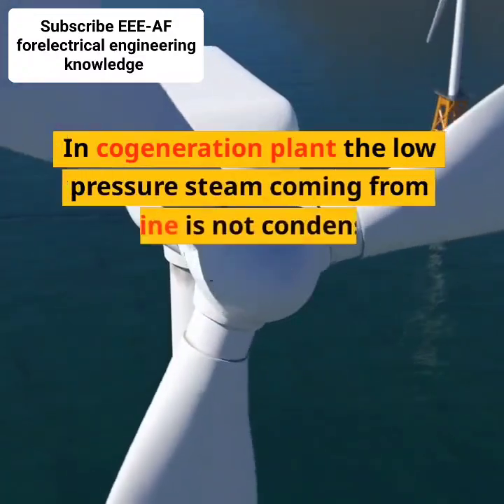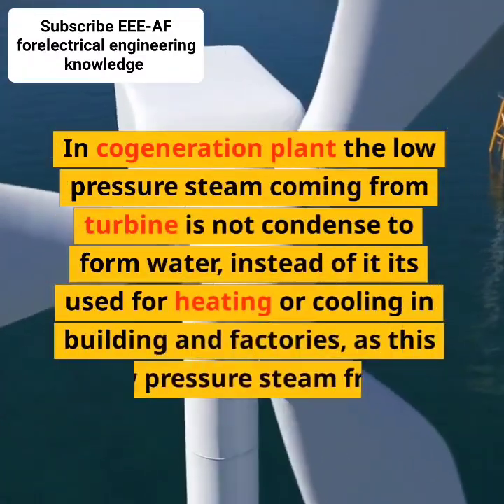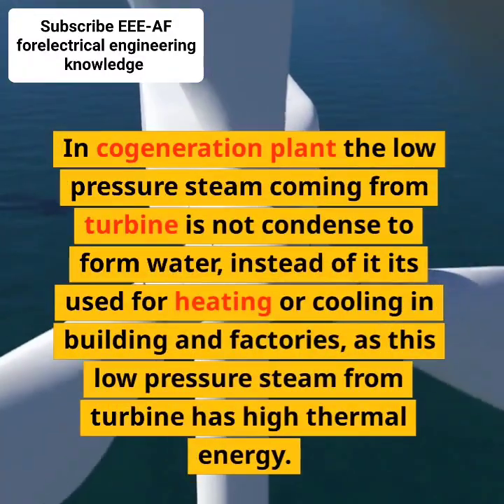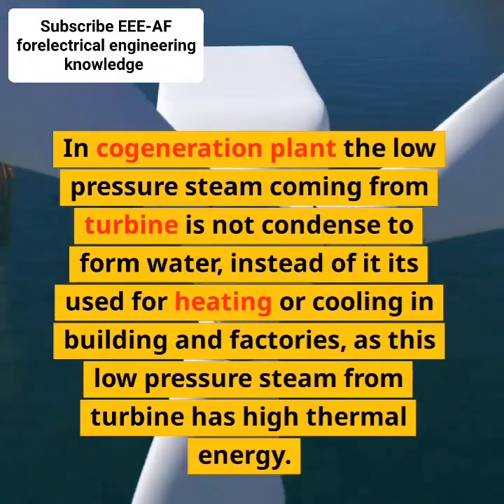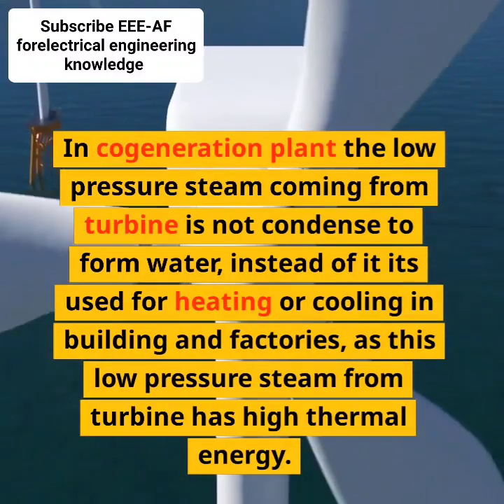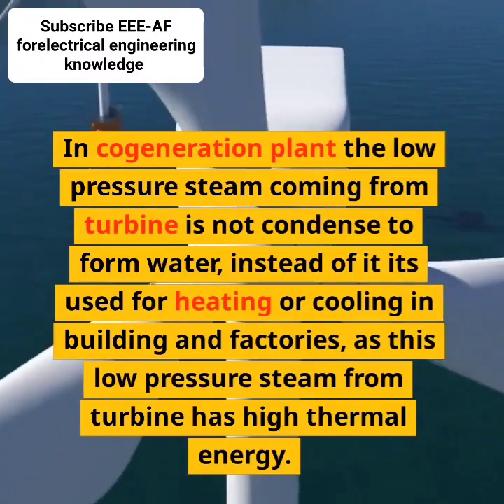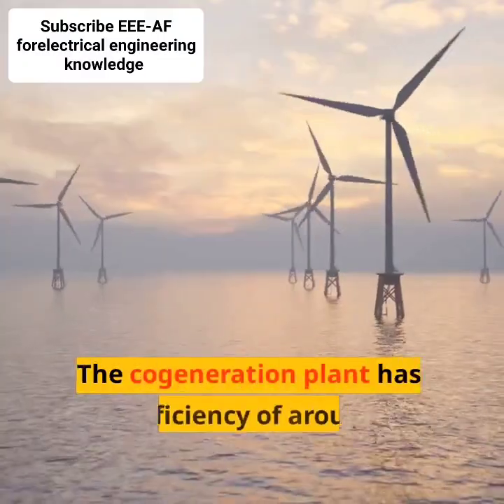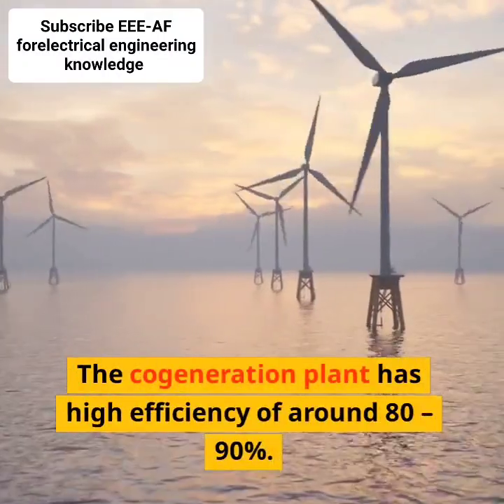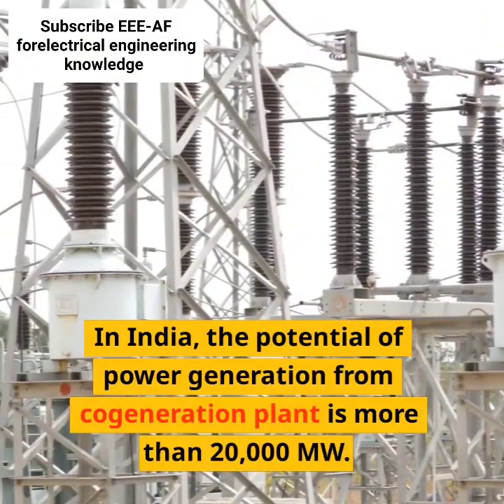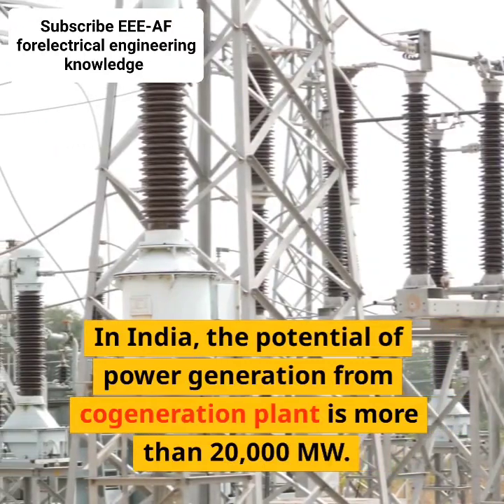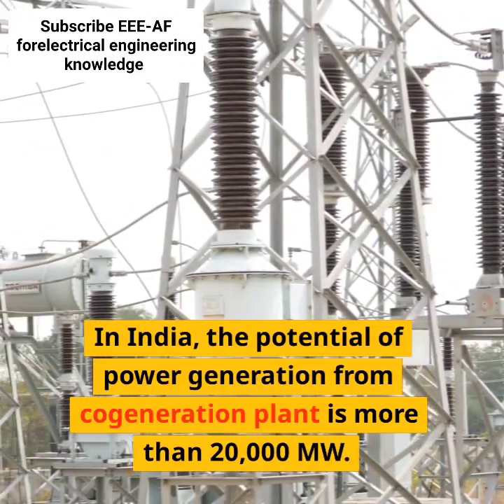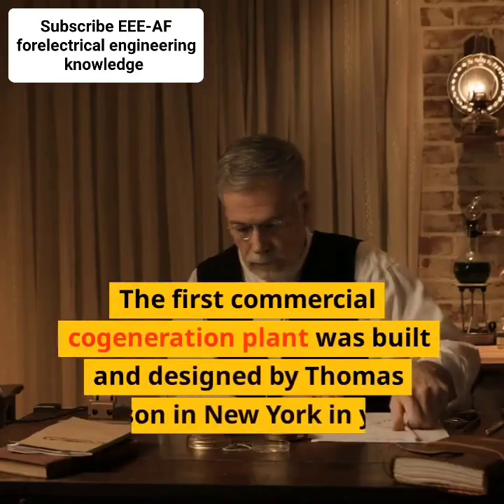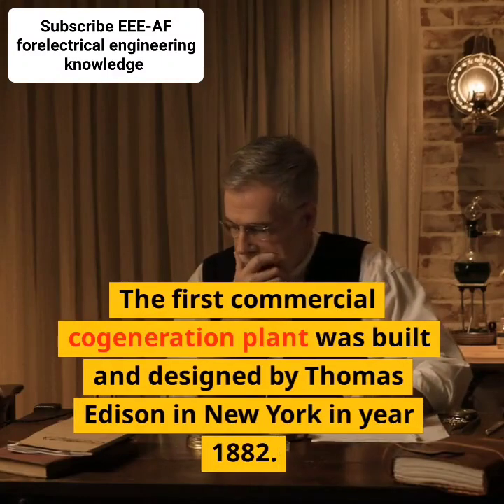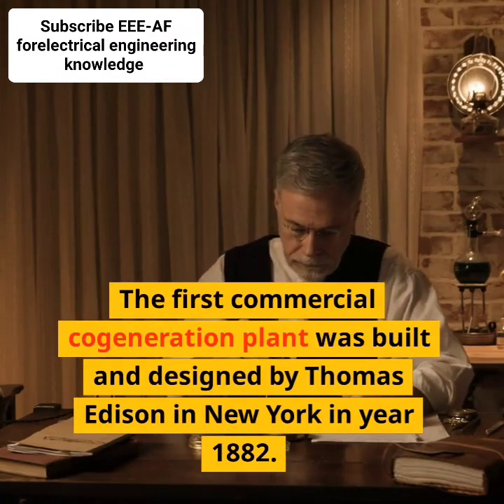In cogeneration plants, the low-pressure steam coming from the turbine is not condensed to form water. Instead, it is used for heating or cooling in buildings and factories, as this low-pressure steam from the turbine has high thermal energy. The cogeneration plant has a high efficiency of around 80 to 90%. In India, the potential of power generation from cogeneration plants is more than 20,000 megawatts. The first commercial cogeneration plant was built and designed by Thomas Edison in New York in the year 1882.